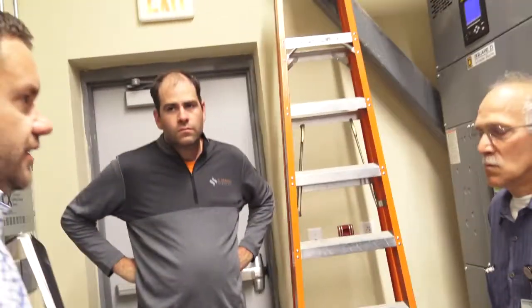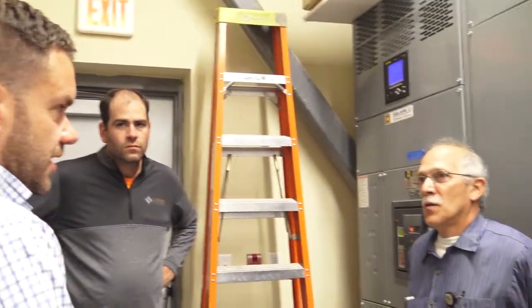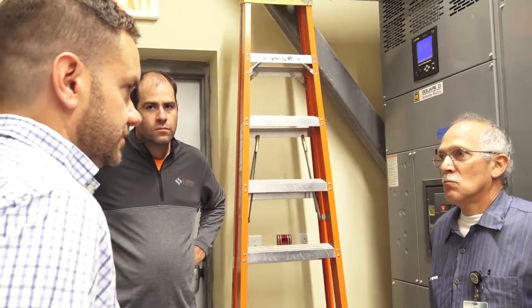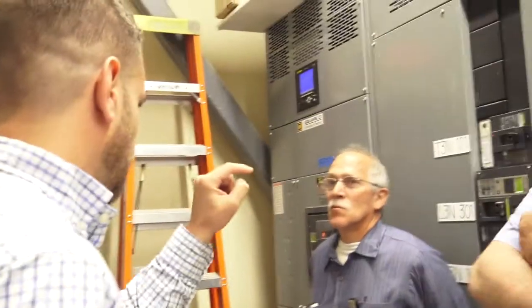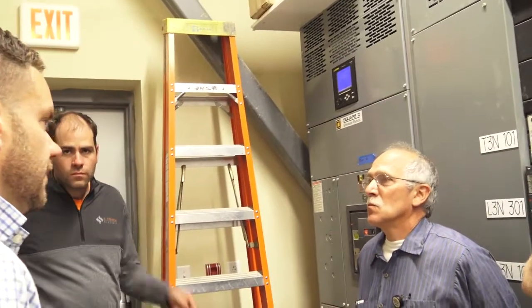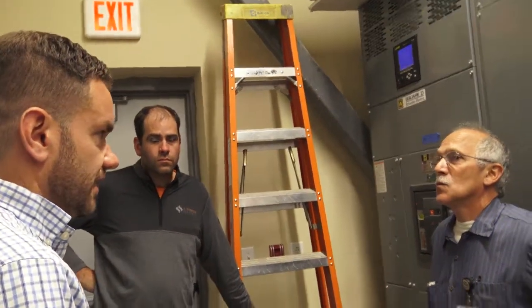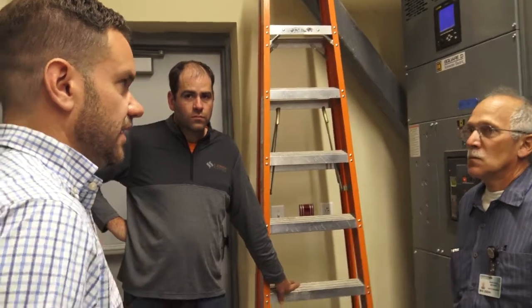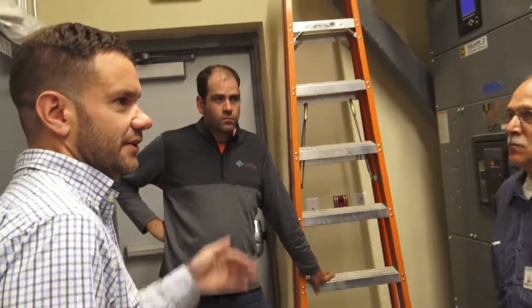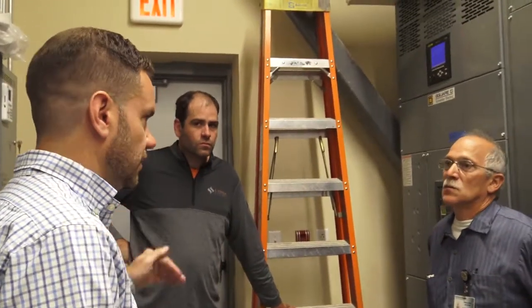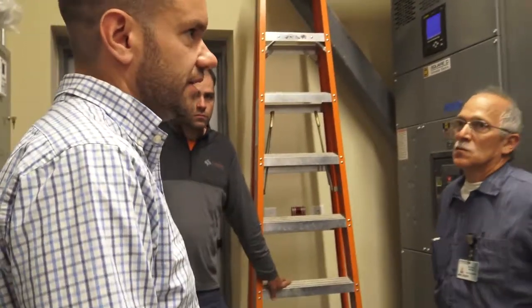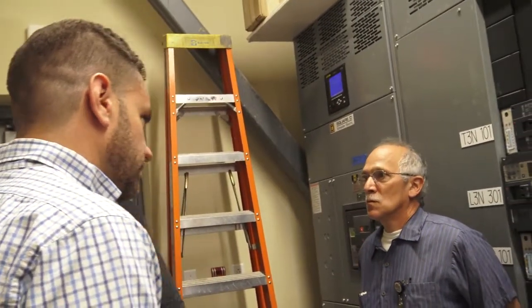We don't have any primary drains on the vault, so the heat trace is on the primary drains. They're all outbound, like a through-wall scupper outbound of the vault. It's pretty imperative those drains remain open, because it's basically a bathtub up there, 4 sides, 2 feet deep. If you had snow or water buildup, you could potentially get a roof leak onto your $4 million accelerator.